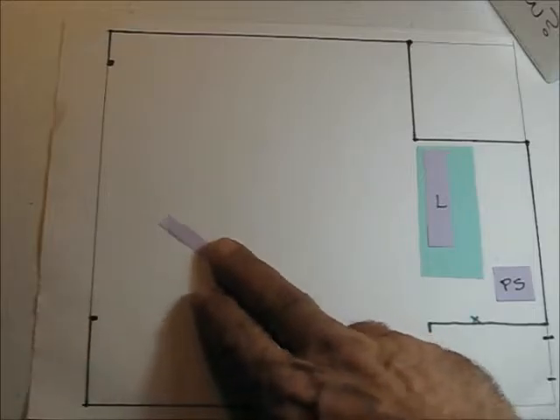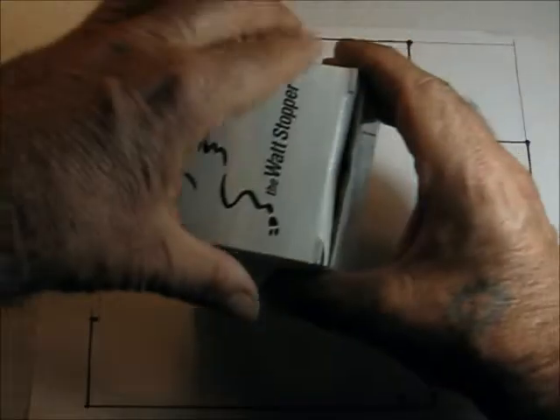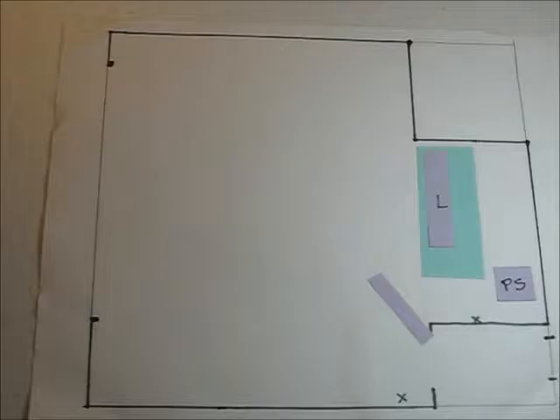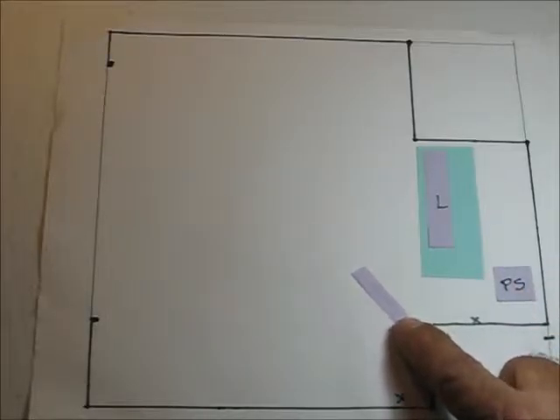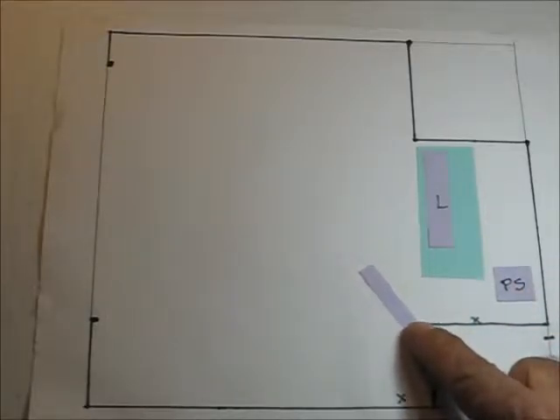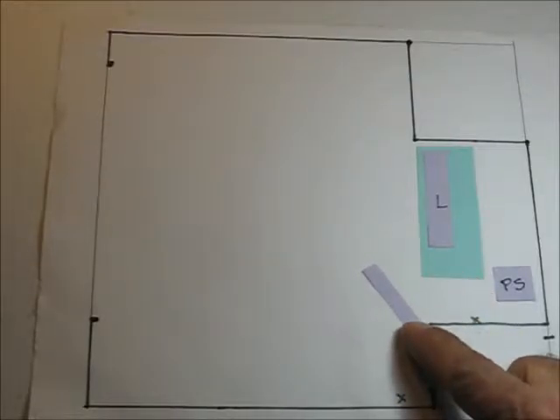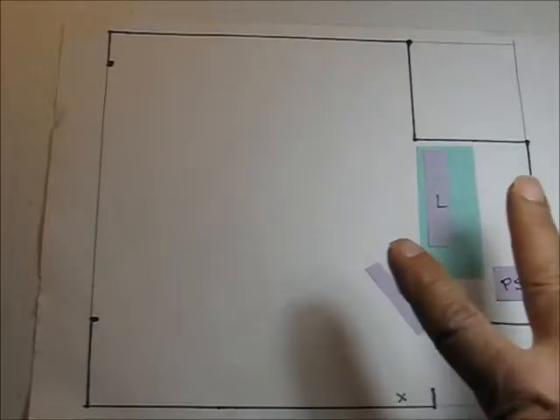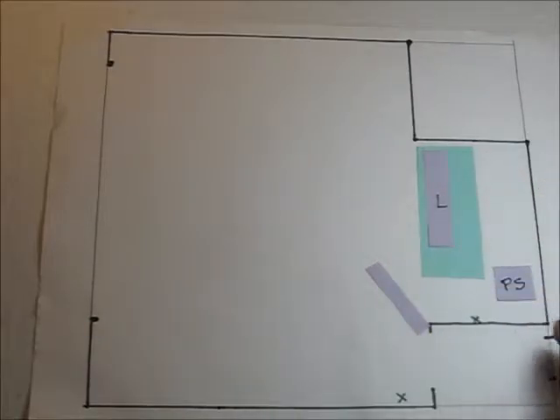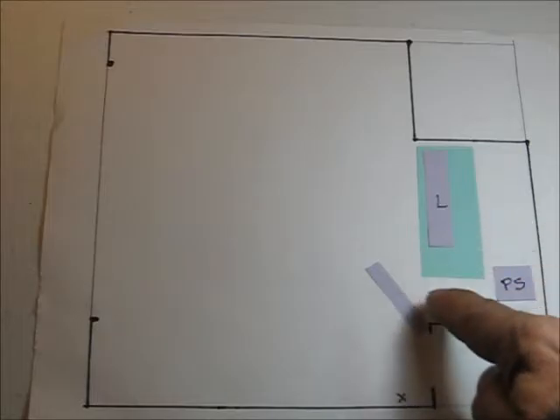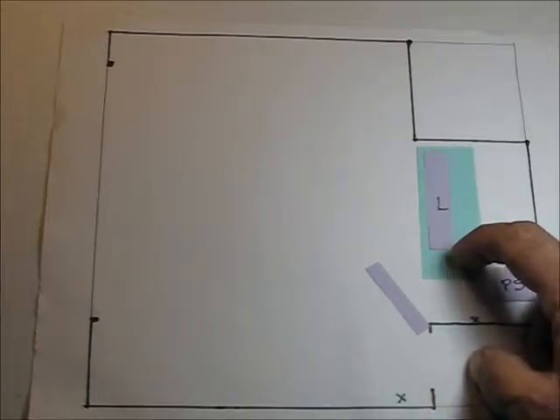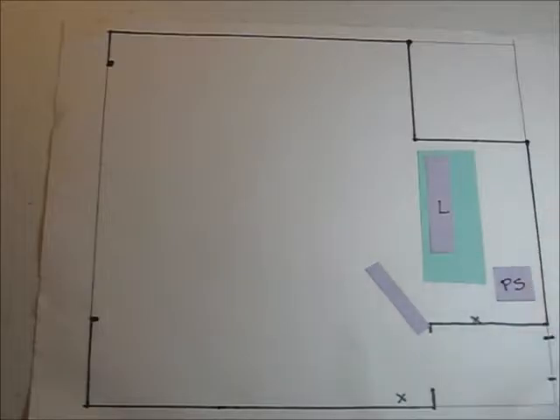Because this is truly a daylighting sensor, we are going to need to set it up for daylighting. And we are going to do that because that's what the manufacturer's instructions say for setup. Because we need to set it up for daylighting, we are going to need artificial lighting to set the second point on its two-point calibration. And right in the middle of all the action, we are going to pick a task location and put a light meter in.